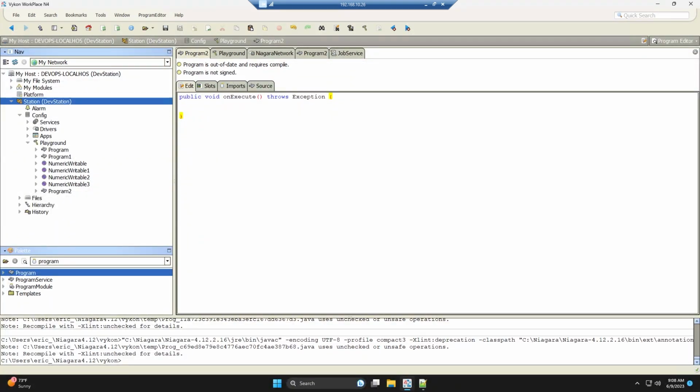So I'm going to create a program that will go out and ping devices that I specify. I run into this a lot with SSL errors and SSL certificates. Let's say I bring a new device, or 100 new devices, into a web supervisor, and they have self-signed certificates or something. You know that if you ping them, it'll come back with a TLS error, and you have to go into the certificate manager, go to allowed hosts, and accept the connection. Then you have to go back and ping the device. So I'm going to create an object that'll ping whichever devices I tell it to.